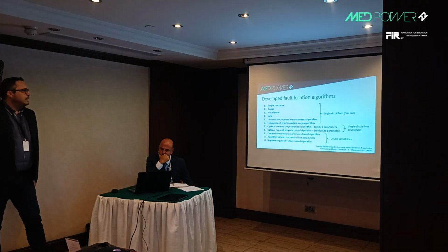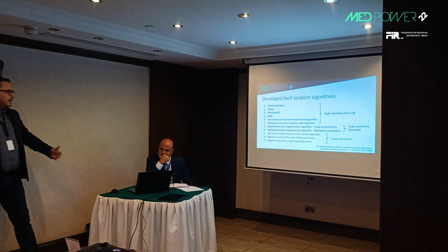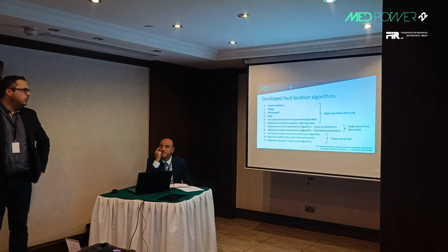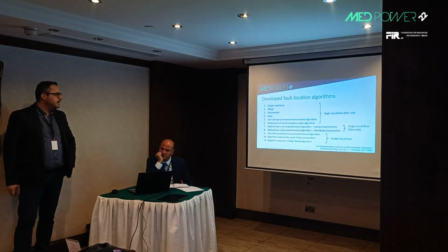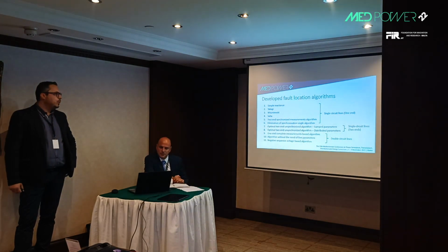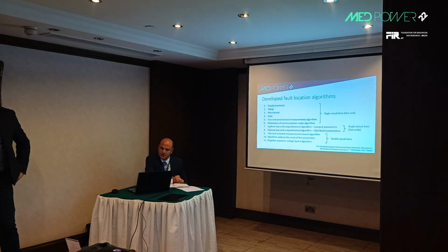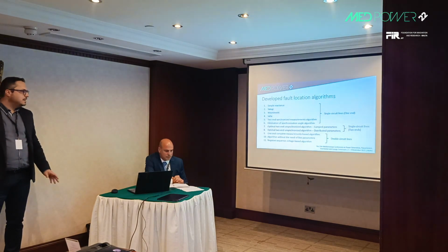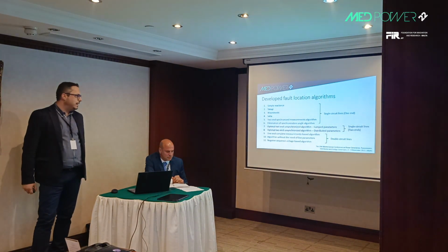The software tool presented in this paper provides to the user 11 different fault location algorithms coded in MATLAB. You can see the algorithms here. There are algorithms that are appropriate for single circuit lines, for double circuit lines, with or without compensation, and they are based on measurements taken from one line end or from both line ends.